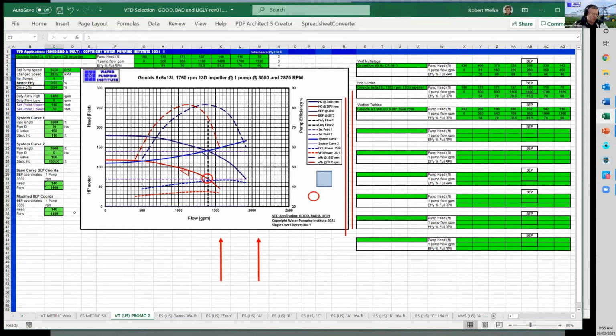It's pretty handy. We're now going to change the pump duty to 1600 gallons a minute at 150 feet head. So we're aiming for this point here. Okay, so that's still on the system curve. So let's go down here to the modified BEP coordinates. Wait a minute, first we've got to change up here. C11 becomes 1600. So these are our new guidelines. That's 1600, and that becomes 150 feet. So that's our new coordinates there.